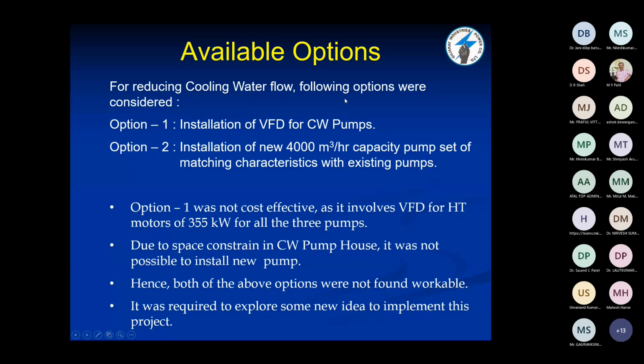Now for reducing cooling water flow, the following options were considered. Option 1 was installation of VFD for the cooling water pump. Another option was the installation of a new 4,000 meter cube per hour capacity pump set with matching characteristics to the existing pump. Instead of a 6,000 meter cube per hour pump, we can install a 4,000 meter cube per hour pump, that is, a pump with 2,000 meter cube per hour less capacity, and hence we can reduce the power consumption. Option 1 was not cost effective as it involves VFD for HT motors, and VFDs for HT motors are very costly. So option 2 was selected.